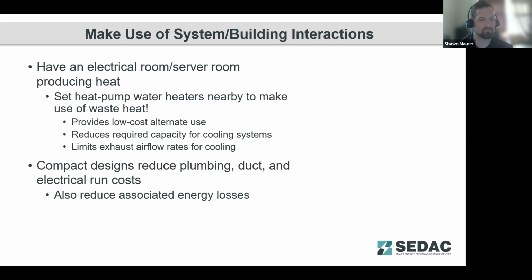Similar things can be done with skyscraper structures where you've got a central shaft for elevators. You could do the same thing for ventilation, ductwork, and things like that. And then they branch out in shorter branches to floors in the building. The more compact your building is, the easier it is to do those kinds of designs. If you have a more sprawling design for your building, you're going to necessarily have longer runs of these systems and greater associated losses with them.